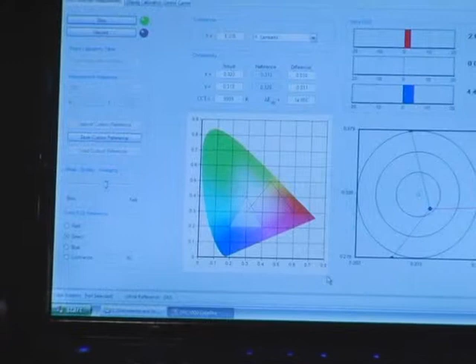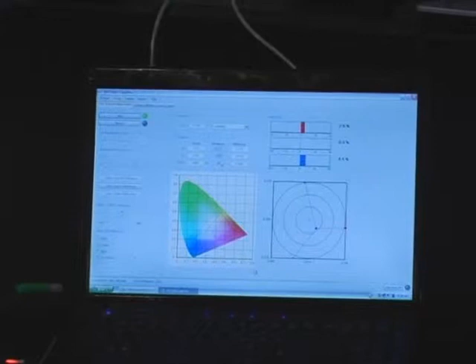So we're measuring the grayscale of the display, whether it's a high white type of test pattern on the screen or a dark gray pattern. We want to balance that point, if you will, to a specific standard. The standard, without getting into a lot of detail, is generically referred to worldwide as the D65 reference. And what a calibrator will do is they'll make these measurements, and in this software interface with the measurement device, it's constantly updating. And what it tells the calibrator, based upon what they see on the interface here, is whether they need to add a color, take away a color to achieve what we generically and traditionally refer to as white balance.